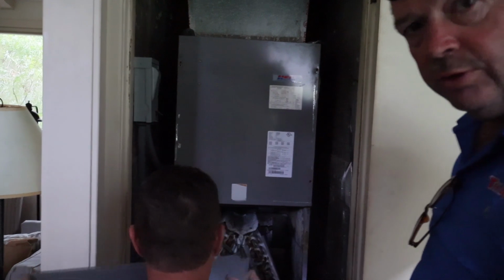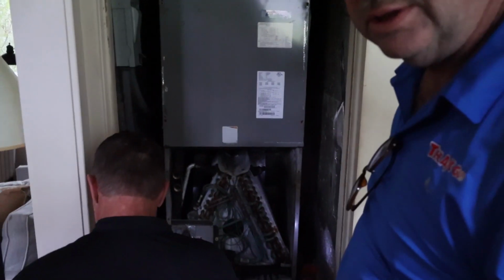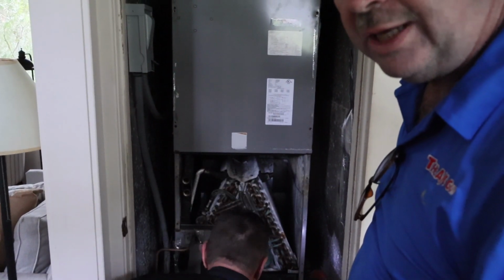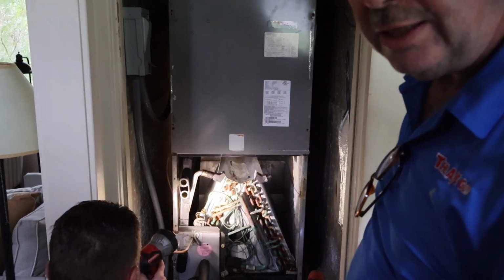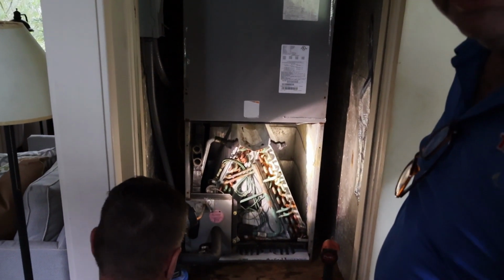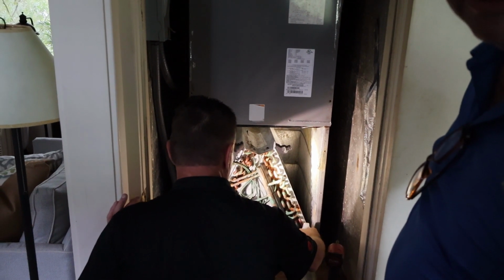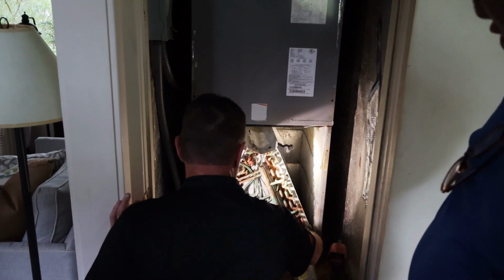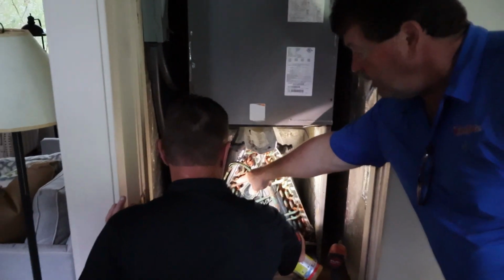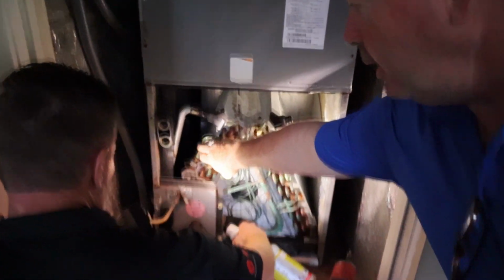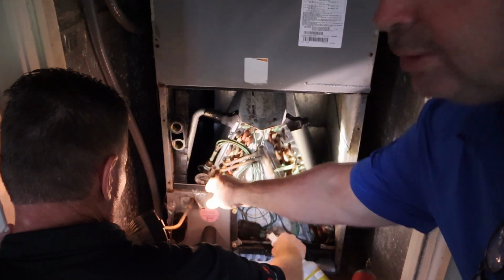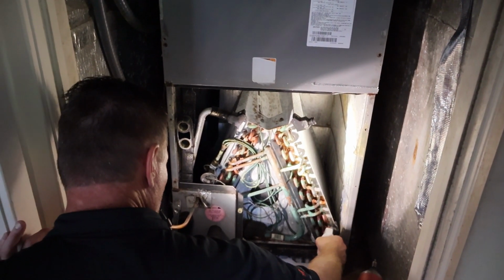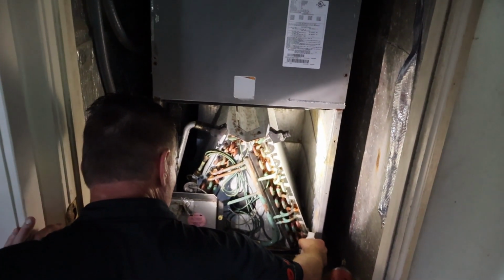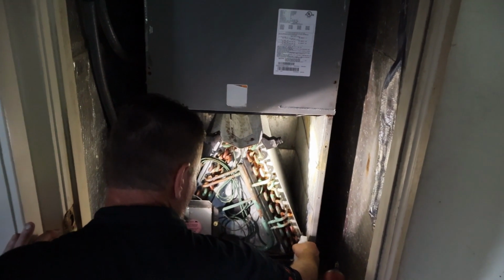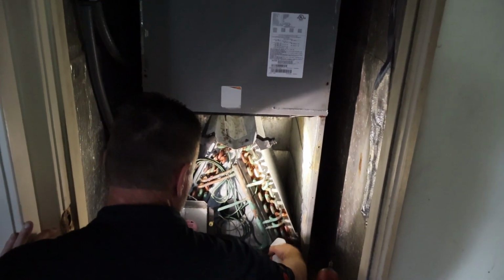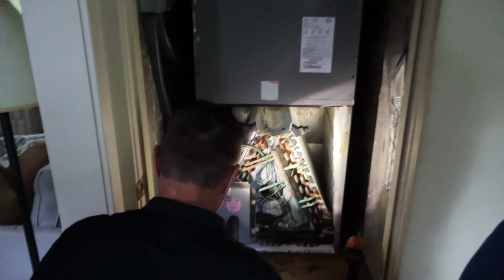Yeah, Dave's removing the door, so we will know what kind of metering device this machine has. So whenever we go outside in a few minutes, we'll be able to know how to check the charge, either by subcooling or superheat. And it appears, if you look at this valve right here, that's an expansion valve. So we'll check the charge by subcooling. It's not a fixed orifice. He's putting more Viper algae reduction solution in the pan to prevent algae growth.